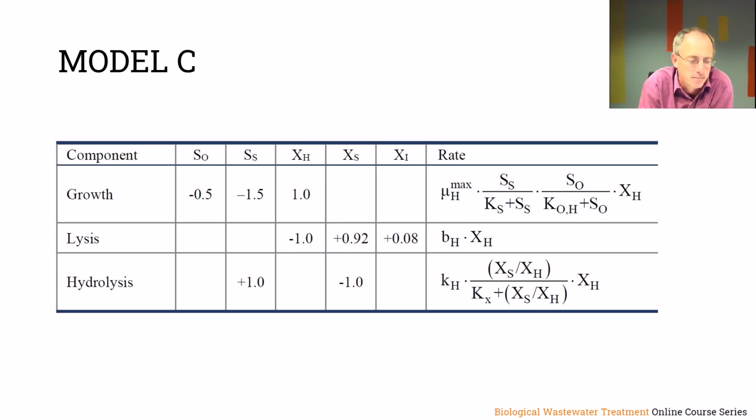And we do something else, because it's also known that especially the cell walls of the microbial cells are very difficult to degrade. And they also accumulate in the sludge. So the content of the cell will all be converted, but especially the cell walls are very difficult to degrade. So if we have decaying cells, we say that about 90% becomes biodegradable and about 10%, or here effectively 8%, is non-biodegradable. It will accumulate also in the sludge.